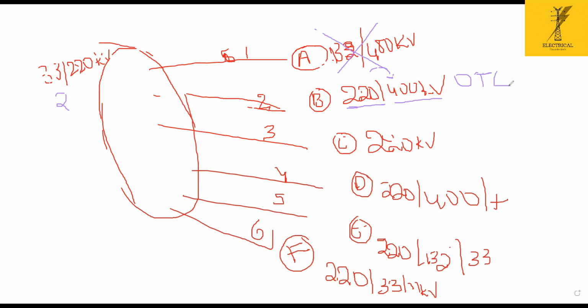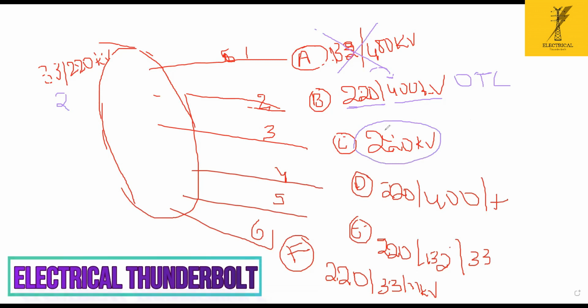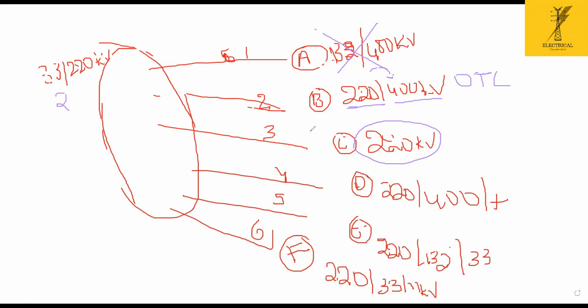So transformer loading. And if I go to the next substation, here it is a 220 kV substation, only line incomings and line outgoings. I am checking whether there is space in the substation or not for integrating your power. So what I am checking is the space. I found there is no space in the substation. So I am checking the next condition, space. I went to the next substation. I find the space. I find the transformer loadings.